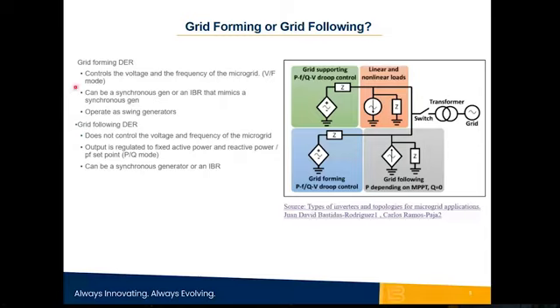A grid forming DER can be a synchronous generator, or it can be an IBR that mimics a synchronous generator. So now with new inverter technology, developers are finding ways to have these inverters mimic the behavior of synchronous machines. And you have now BESS systems, for example, that can behave to some extent like a synchronous machine and be grid forming. These operate as the swing generators because if you have multiple generators in island load share, whatever the load is, they ramp up and down as the load changes. So they're swing machines.